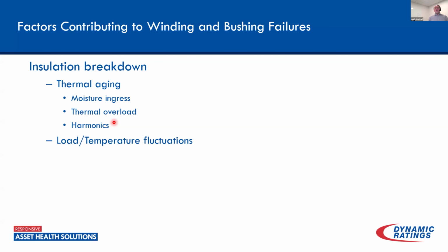Harmonics is probably the piece that people don't focus on enough when it comes to renewable applications. Back in my early career, I heard a lot about transformer failures, but this was more in high-rise apartments and office buildings and things like that. They were focusing more on the third harmonics and the impact they were seeing, with wiring burning up and so on. Harmonics can have a significant impact on the thermal aging of that insulation. I'm going to cover that in more detail because, ironically, the harmonic profile that we're seeing from the renewables has shifted and changed over time, and that can have a significant impact.